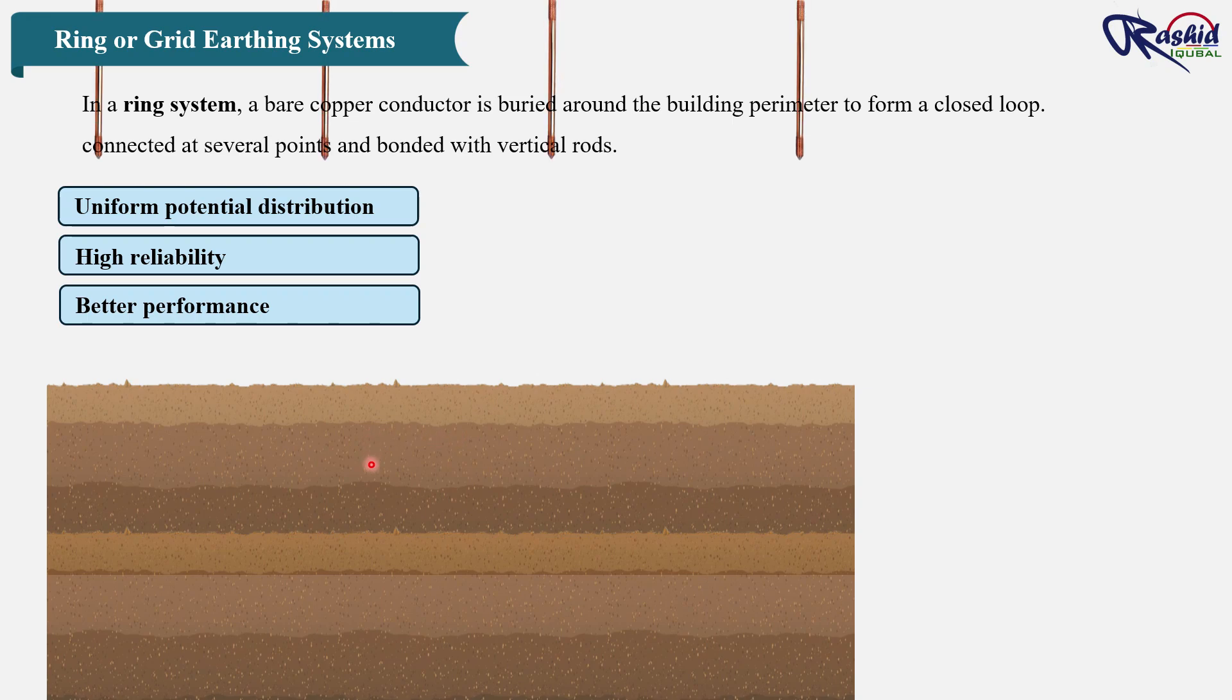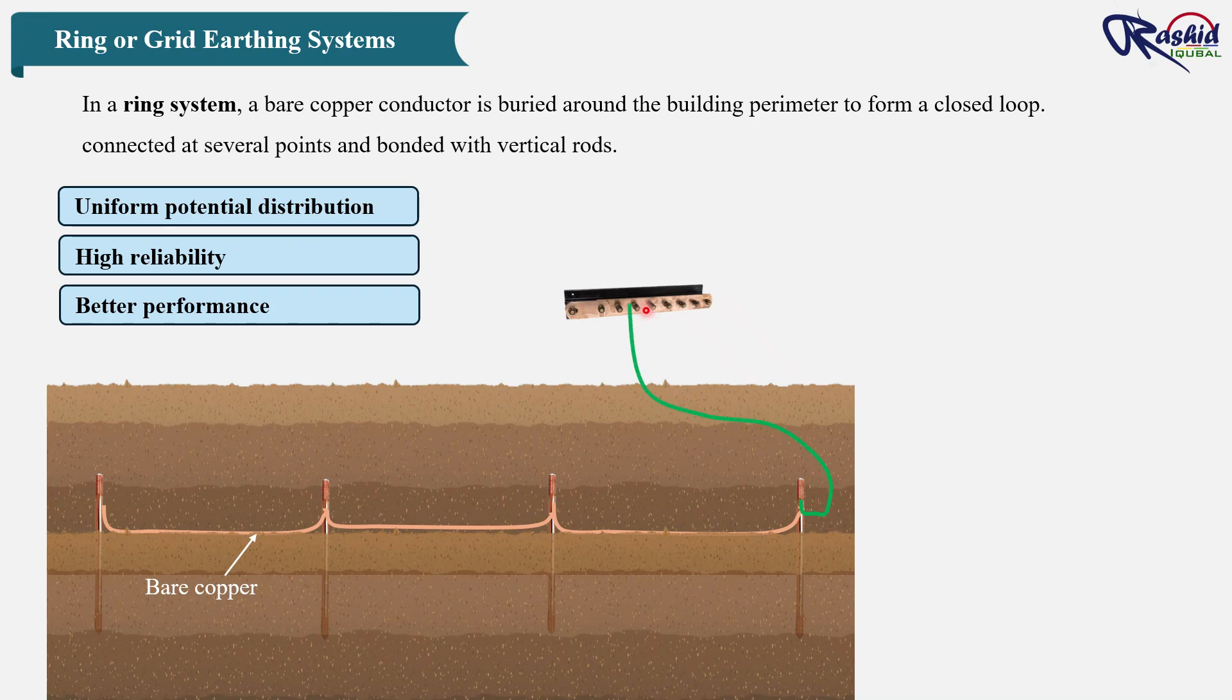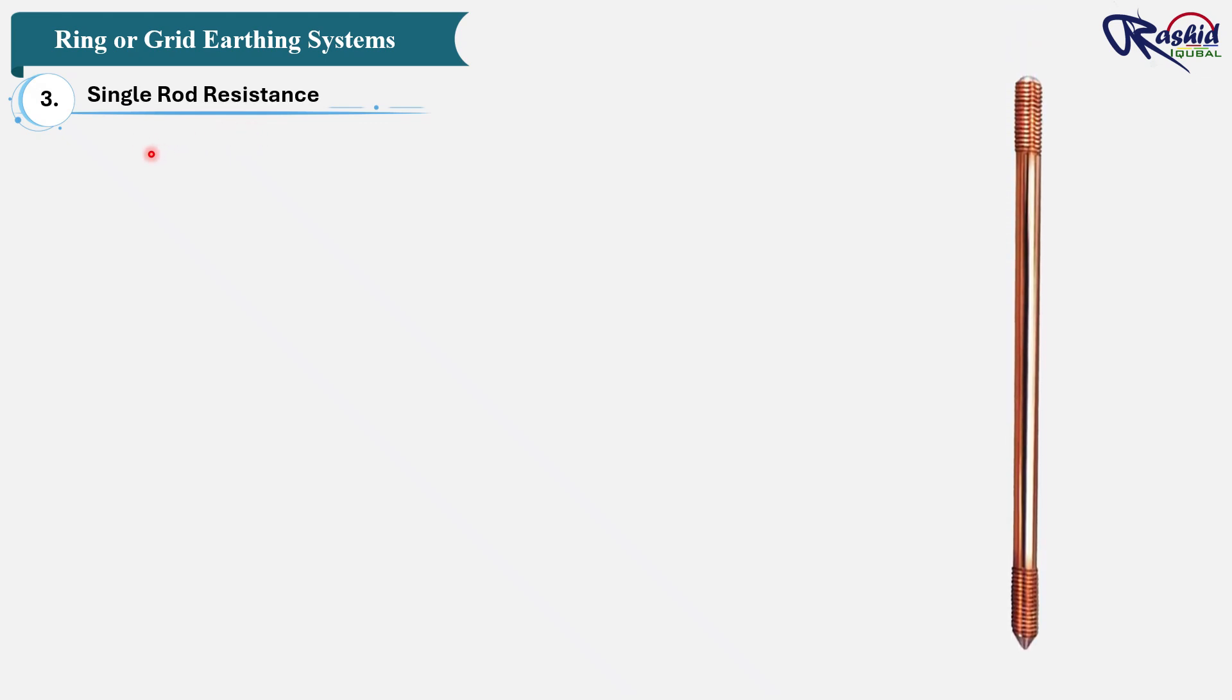In practice, the earthing system for a large building is usually a combination of these methods. Typically, we have multiple vertical rods around the plot, a buried bare copper conductor ring interconnecting all rods, and main earthing conductor linking the buried grid to the main panel. But now the question is, how do we decide how many earth rods are required, and what size of bare copper conductor should be used for the buried ring? To find that, we first need to calculate the resistance of a single earth rod. Once we know that value, we can estimate how many rods will be needed to achieve the required total earth resistance, and then we will calculate the size of buried copper conductor accordingly.